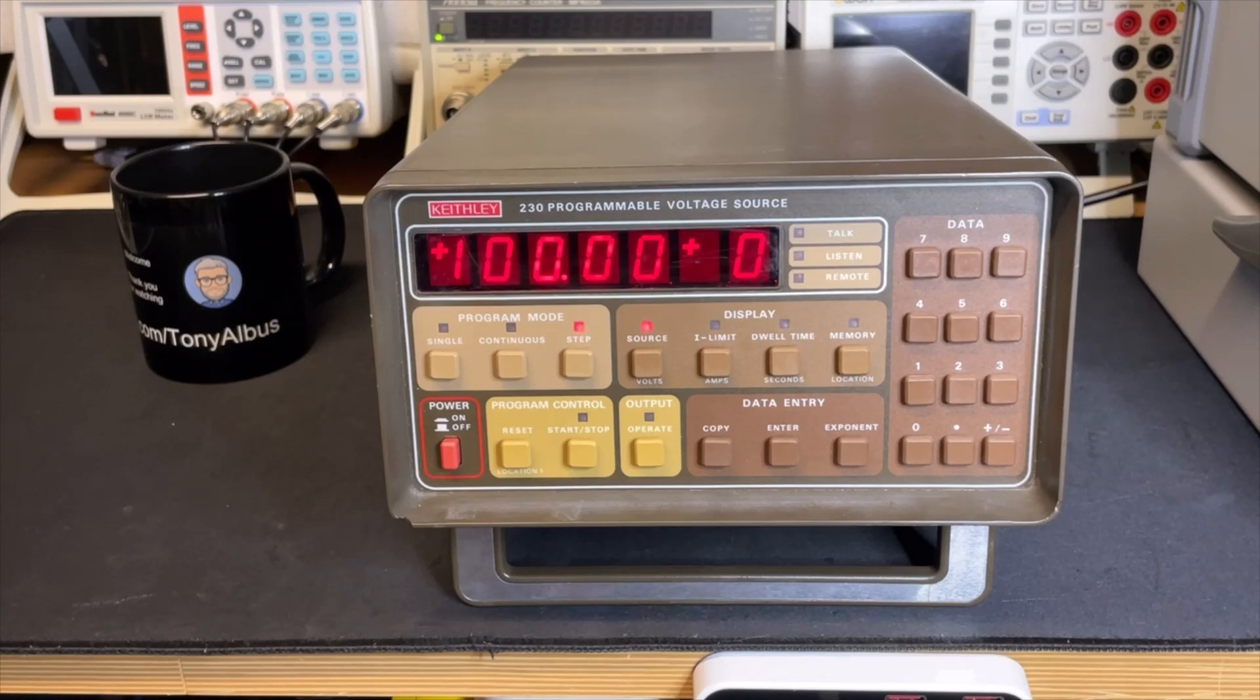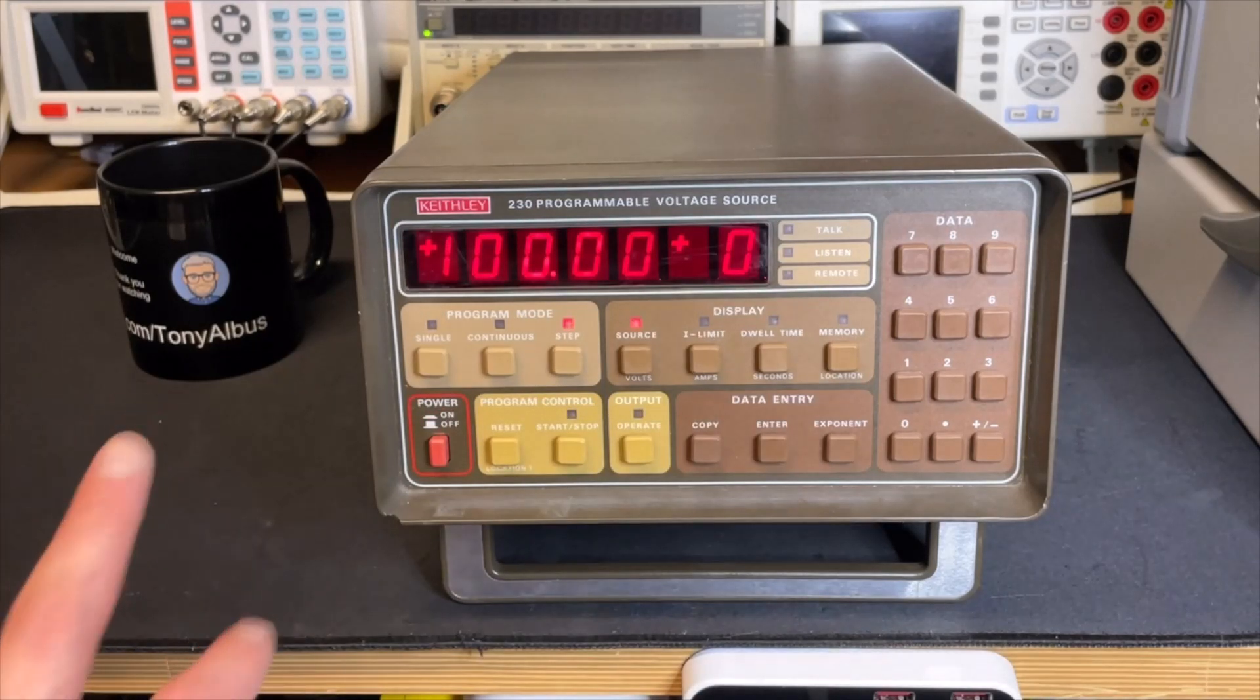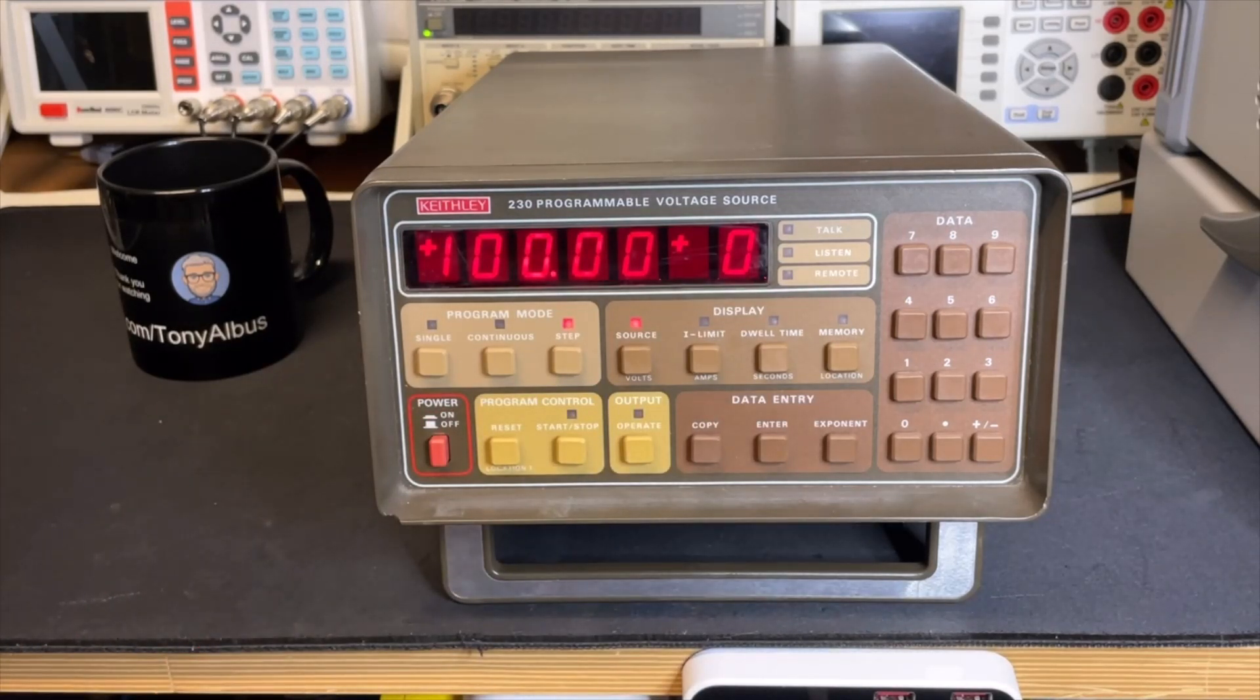And it is quite accurate. It is 0.05% on most of the values, except for the 100 millivolt. There it is 0.075. It is programmable. So that means in this case that you can program 100 steps.